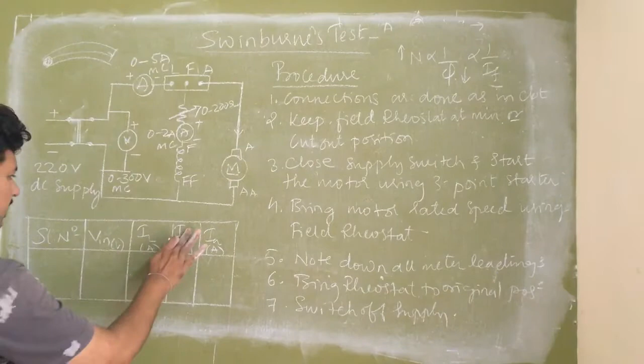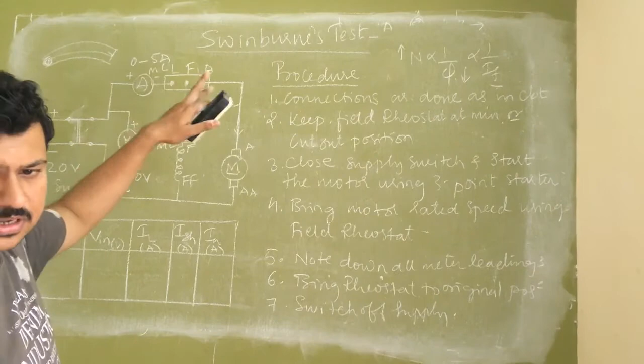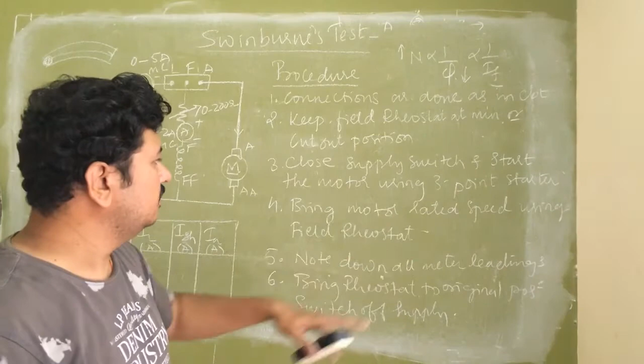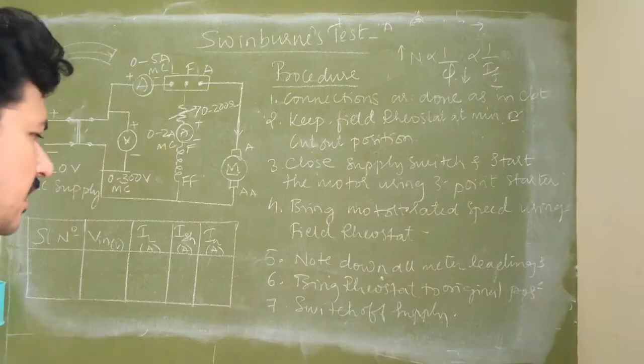So to decrease field current, I should increase the resistance. When I start increasing the rheostat position, field current starts decreasing and speed starts increasing. I should do this until the rated speed is reached. Bring the motor to rated speed using the field rheostat. Once the motor reaches its rated speed, note down the readings of all the meters.